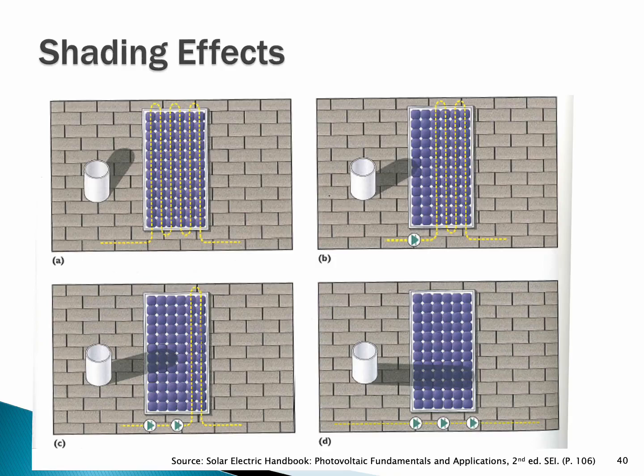When there's full sun on the module, we have full electrical production on each cell that is connected together in series. When the sun starts shading the side of the module, we lose that cell group. And so these things called blocking diodes block off this cell group and reroute electrons around it. So it's like a detour. And so the module is still functioning, but it's lost 1/3 of its voltage output.